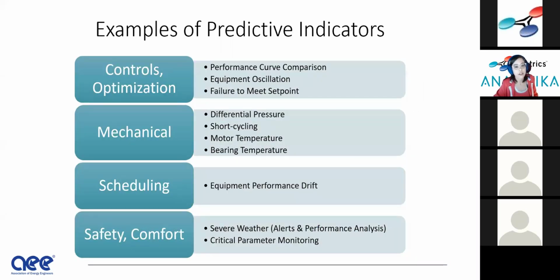So I won't go through every single one of these examples because we're about to show you some examples. But predictive maintenance can include observation of equipment performance drift, for example, vibration analysis, critical parameter process monitoring, monitoring equipment during severe weather conditions, and predicting periods of time where that might be an issue. That's very important, especially when you consider the possibility of frozen coils and people being uncomfortable during severe weather, outside of ASHRAE conditions. And we'll talk about that in an example.